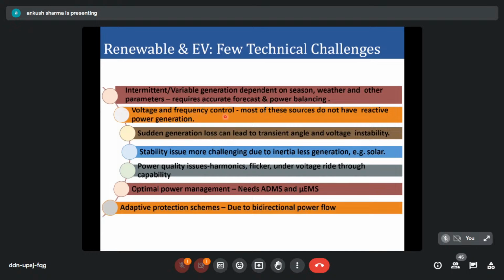Then voltage and frequency control, because most of these sources do not have reactive power generation. Although new converters which are coming up in the market now have converter control with reactive power generation, we have a lot of such installations in the solar, in the distribution and transmission system, where the solar generation happens with the help of first generation or second generation inverters, where we do not have reactive power management capability. So this again poses the challenge of how you will control the voltage and frequency of the system.